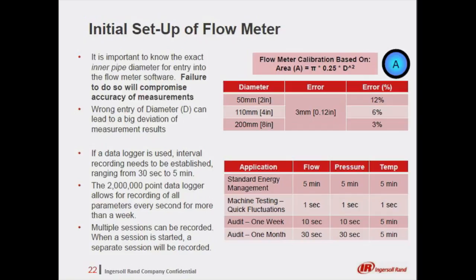The flow meter's internal pipe size calibration is based on a calculation of internal area of the pipe with other variables including airflow speed, temperature, and pressure. Entering the wrong pipe diameter, even as little as 2% error, can lead to more significant deviations in readout results.